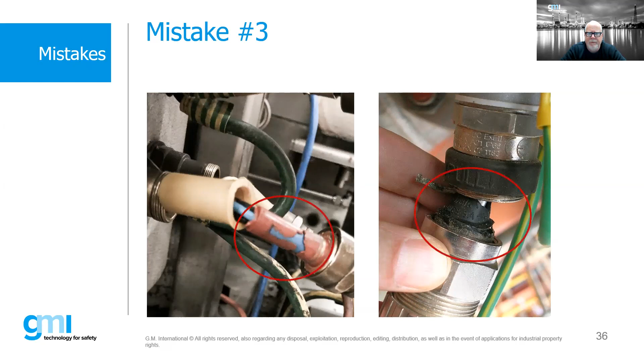Here's an example to throw out to everybody, and I know you can't really answer it, but is this a mistake? We have two different cable glands, same manufacturer, going into a flame-proof enclosure. The gland on the right-hand side is a barrier gland, meaning it has a compound material. The gland on the left-hand side is not. Would that necessarily be a mistake?